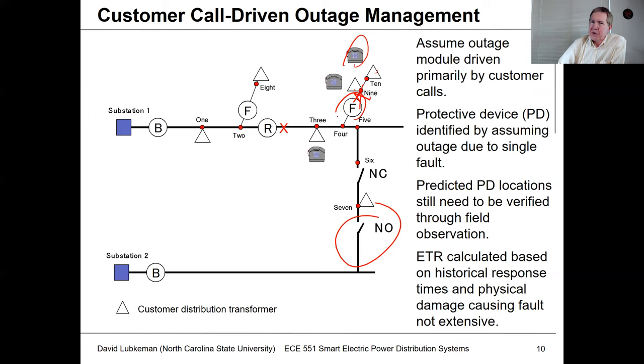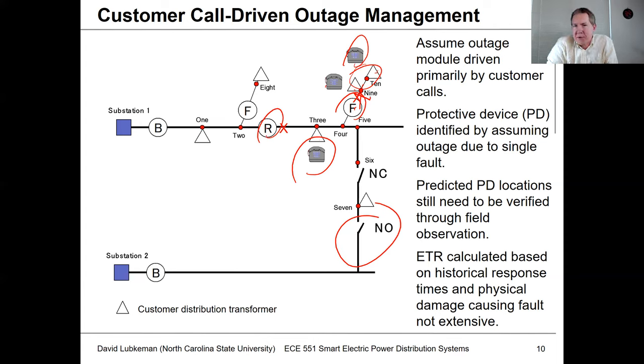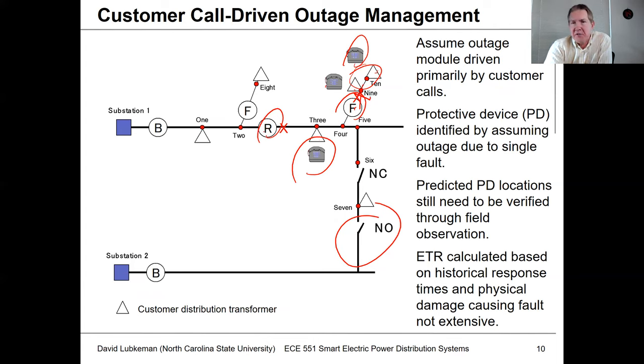Utilities want people to call in quickly — the faster they call, the better — because the utility is trying to figure out the nearest upstream protection device that operated. If only the customers below the fuse call, they ascertain it's a fuse. If those customers call in plus another customer on the main feeder, we start to deduce it would be a recloser. Most outage management systems assume just one protective device is causing the fault, which makes it harder to track multiple simultaneous outages during storms.